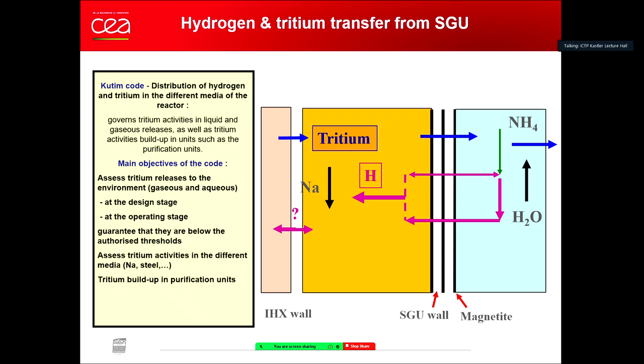So we have developed, strange idea, but we have developed a strategy to inject in the secondary sodium continuously a very small amount of hydrogen in order to reach the right level and then to trap the tritium. So it means that for Astrid, one of the duties of the cold trap is to trap this injected hydrogen, added specially to trap the tritium. Yes, you understand? So it's very strange. We did that quite recently. We did a PhD and developed the process up to 2 years ago.